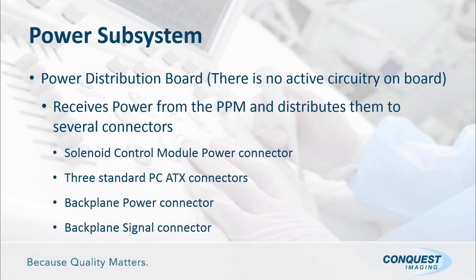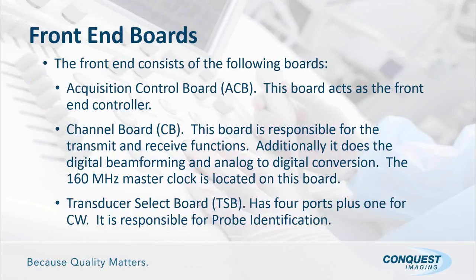The last portion of the power subsystem is what we call the power distribution board. It does have some neat things on it, but the one thing that you need to understand is it doesn't have any circuitry on board. Because of that, it really is not a high failure item. It basically gets its power from the platform power monitor and distributes it to the connectors I have listed: the solenoid control module, your PC ATX connectors, your backplane power connector, and your backplane signal connector. So those are just the connectors that it distributes power to, but it's really not going to be a high failure item. So let's talk about the front end boards.